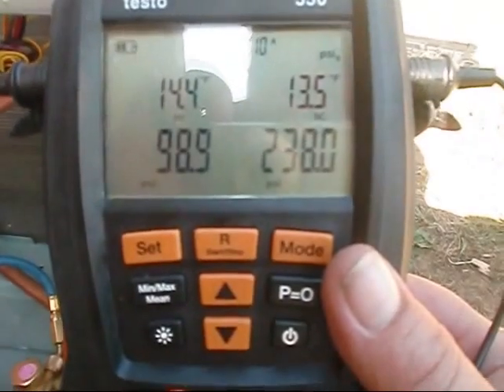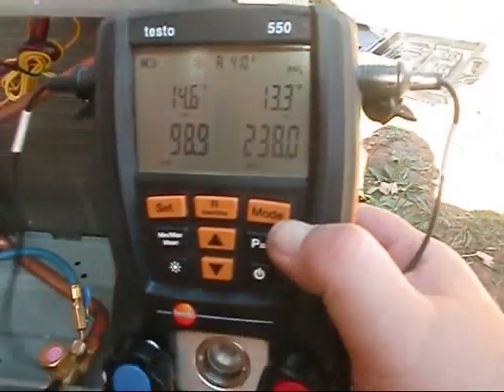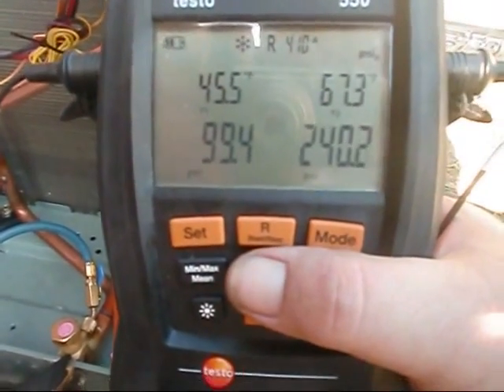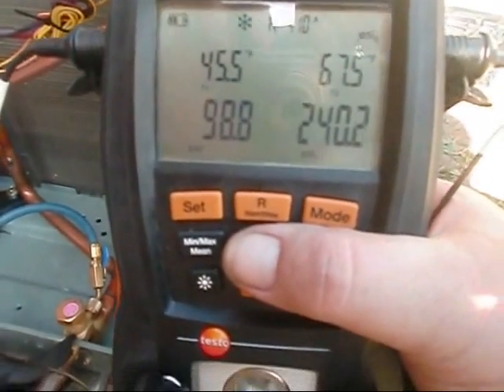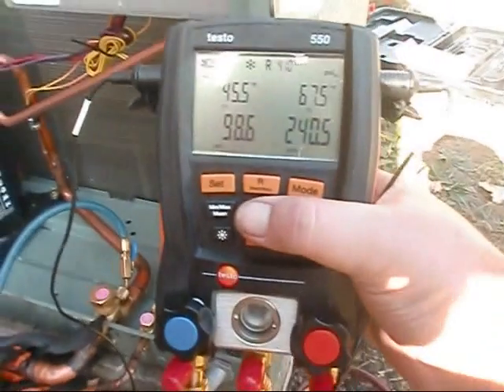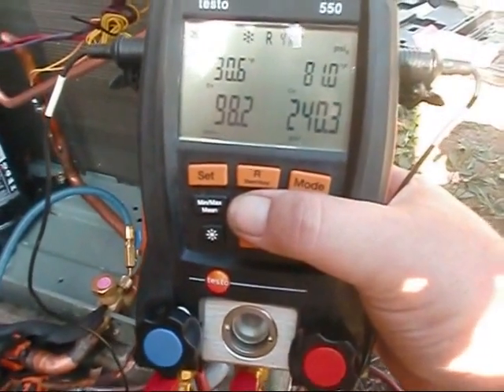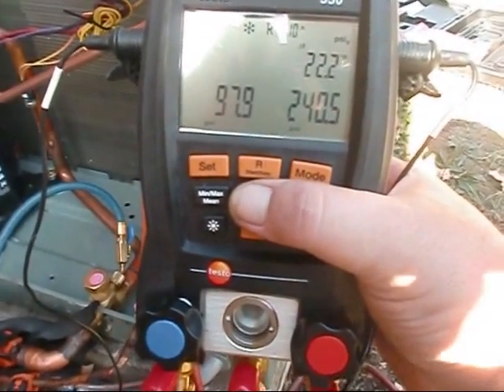Alright. Superheat: 14.4. Sub-cooling: 13.4. 98 PSI on my suction, 238 on my liquid. Suction line temperature is 45 degrees, liquid line temperature is 67 degrees. Evaporator temperature is 30.6, condenser temperature is 81.0. Delta T is 22.2.